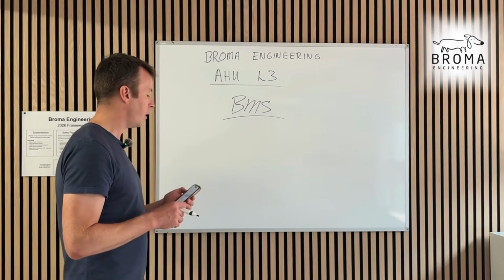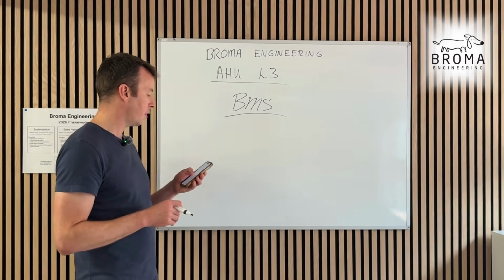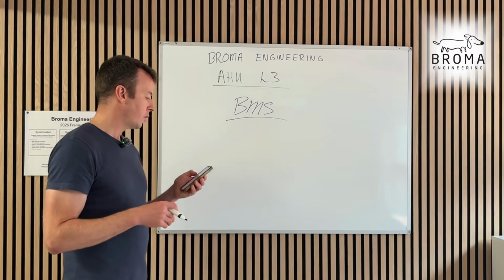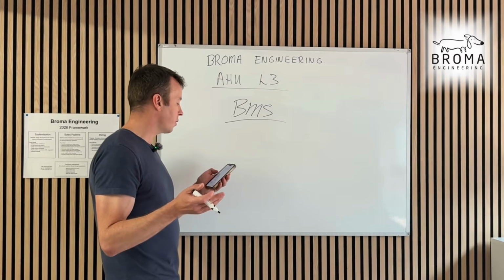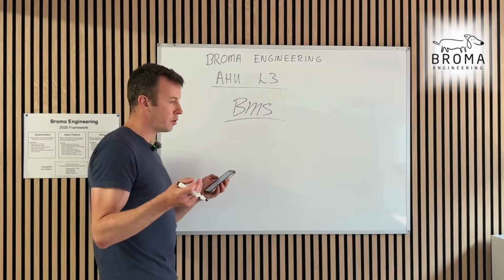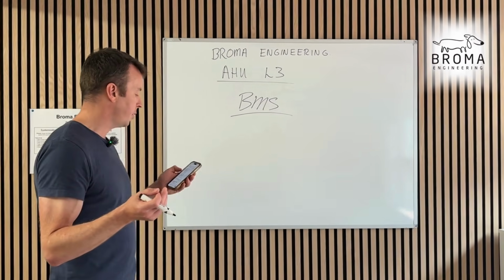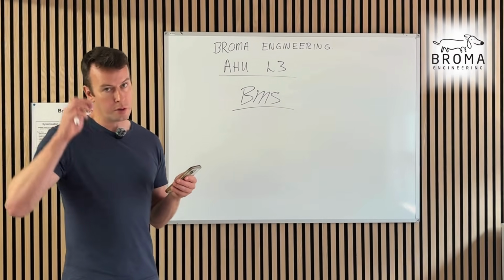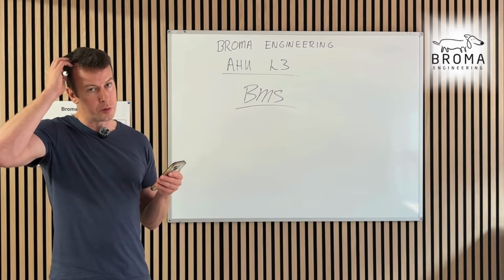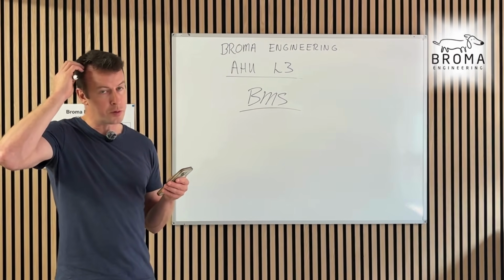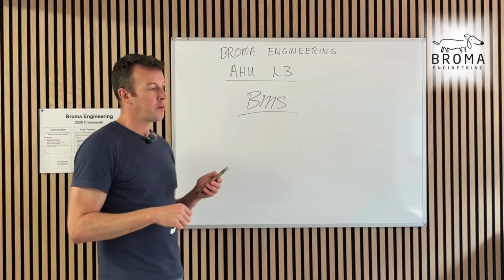So what are they doing? Digital inputs, digital outputs, analog inputs, analog outputs, sensor calibration - very important. Valve feedback too, so we make sure the valves are working. When we tell a valve to open 30%, 60%, 90%, but it's actually doing 25%, we have to verify all of that.